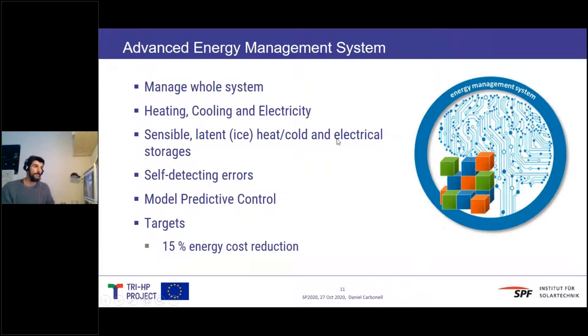On top of this, we have an advanced energy management system that will control the complete system, including heating, cooling, and electricity. It also manages the sensible and latent heat, cold, and electrical storage. It has self-detecting errors at the heat pump level, and it uses model predictive control to decrease the energy cost by 15%.